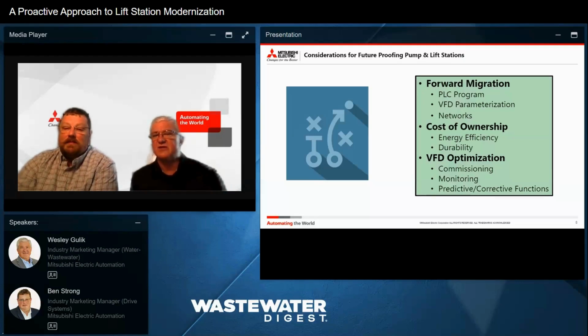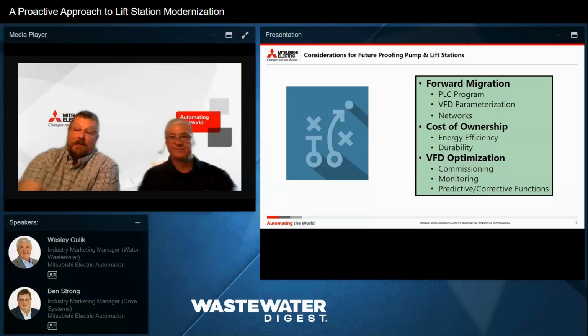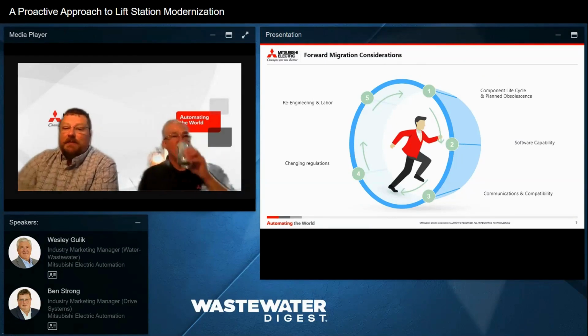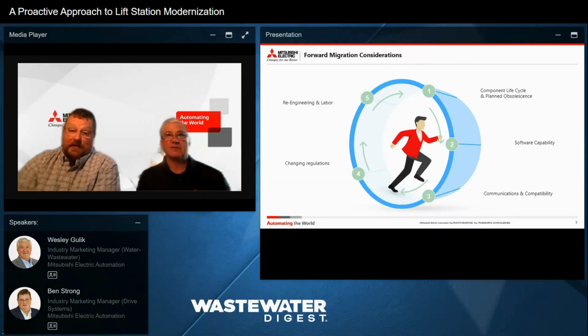And then the commissioning. Some manufacturers will offer factory commissioning, because typically they feel that the factory is going to be the expert at optimizing that system to my pumping station. Then, what type of monitoring are you looking for? Is there a SCADA system in place now, or are you looking to implement one? And then the predictive features are in place, but you need to close the loop, even though this data is coming back. What do you want to do with that data? Absolutely. I think most modern devices will predict their own death, but sometimes we don't use that information, or we're not aware that our drives and our PLCs and our HMIs all have these features.